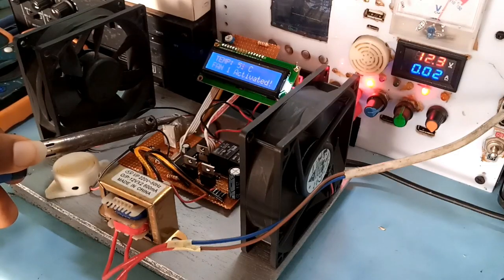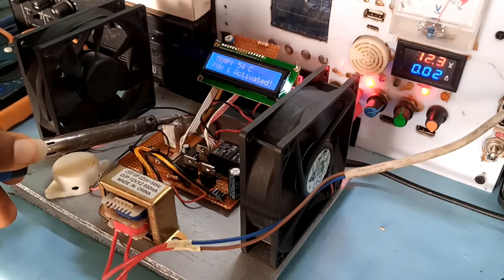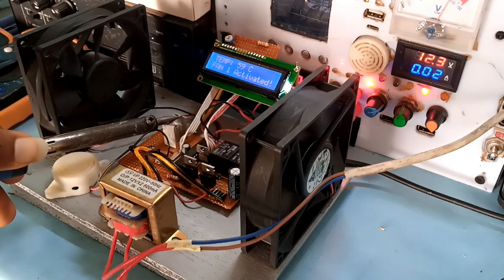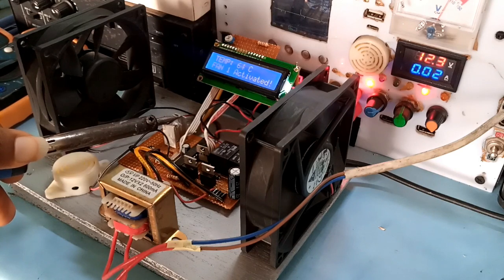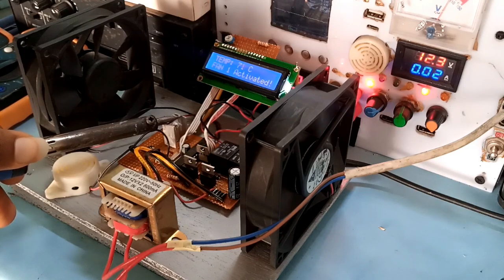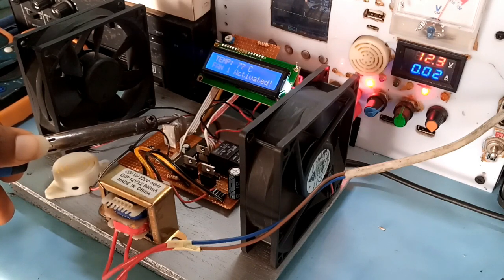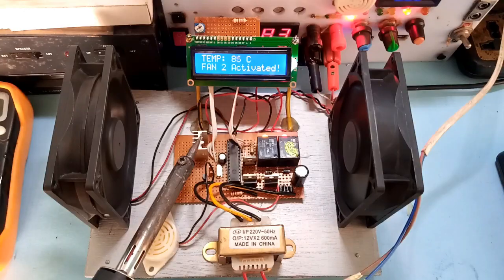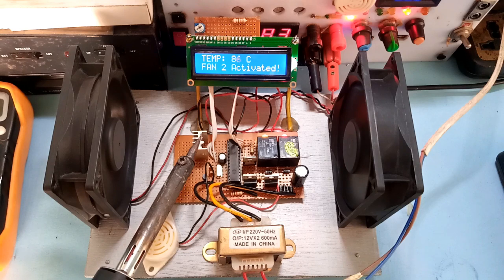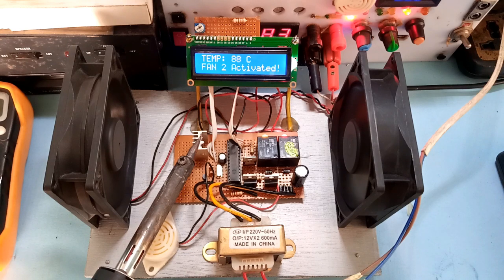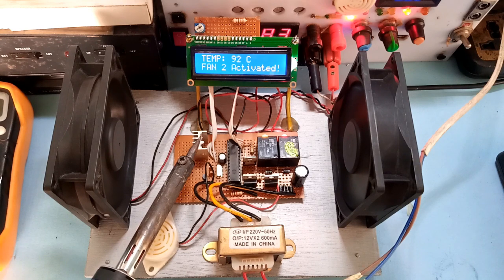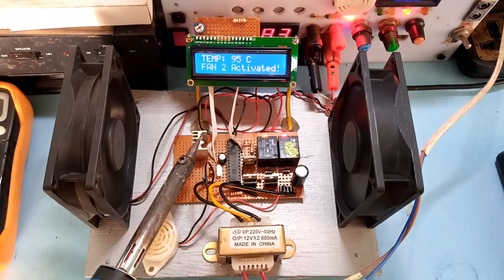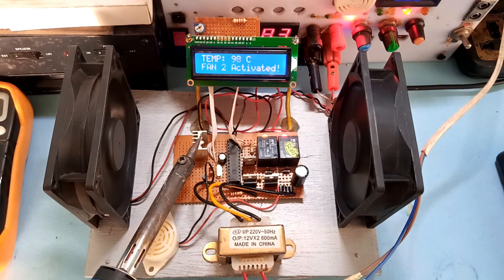The temperature keeps on rising to 80 degrees centigrade as the next fan turns on. And at 100 degrees centigrade, the system cuts the power for the fans as programmed.